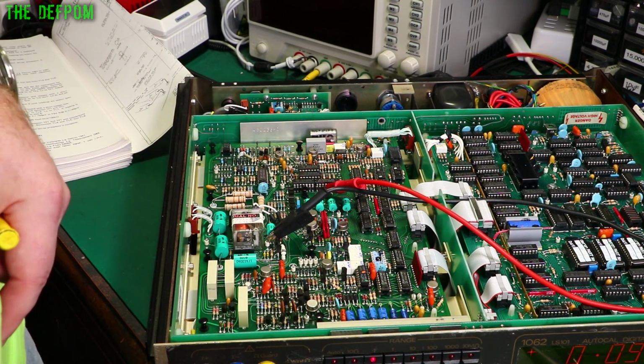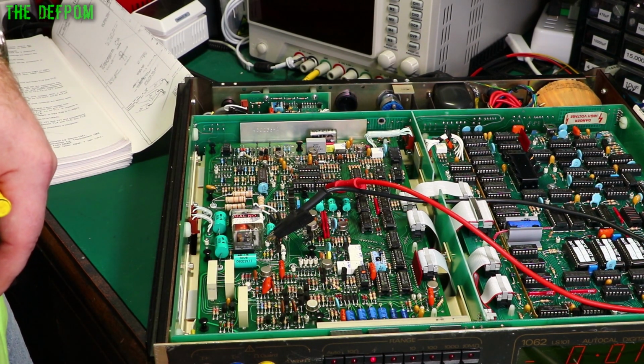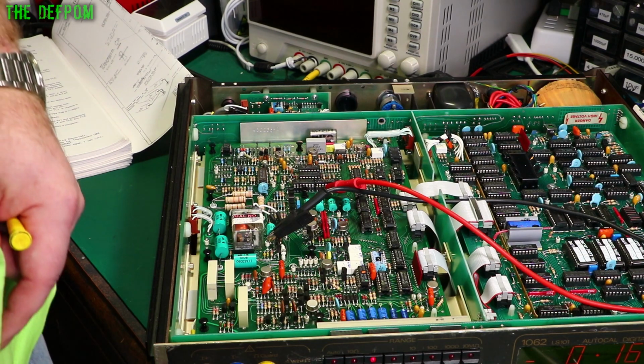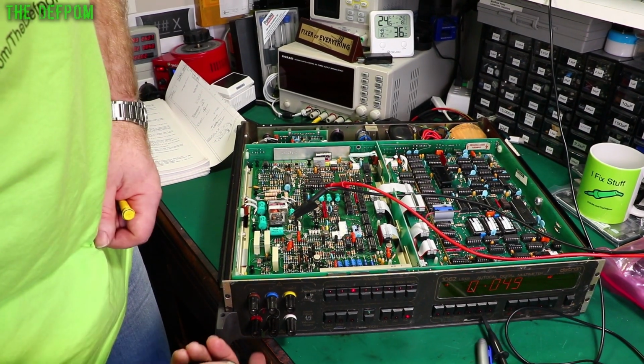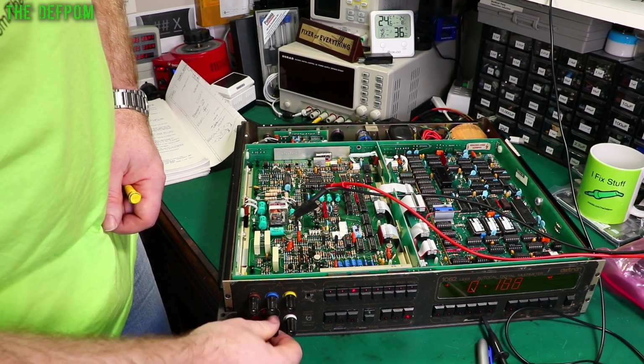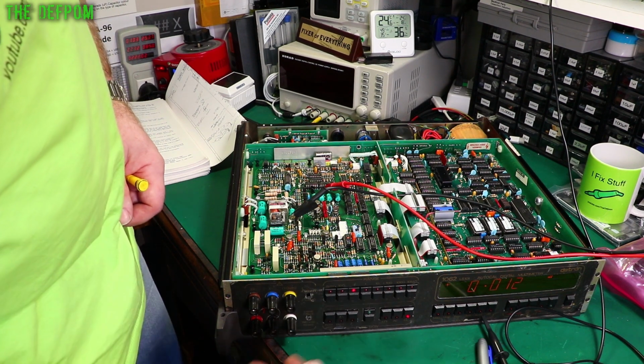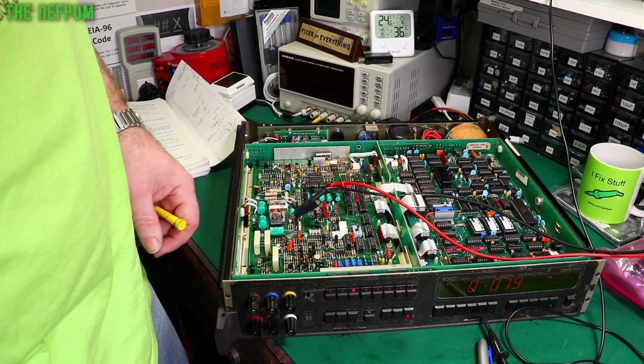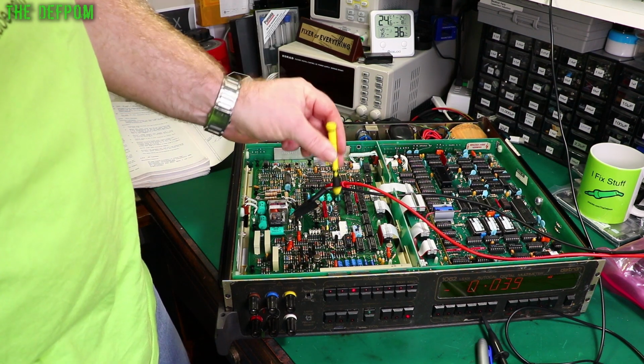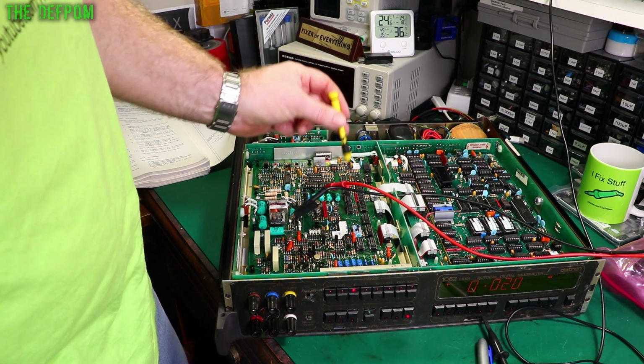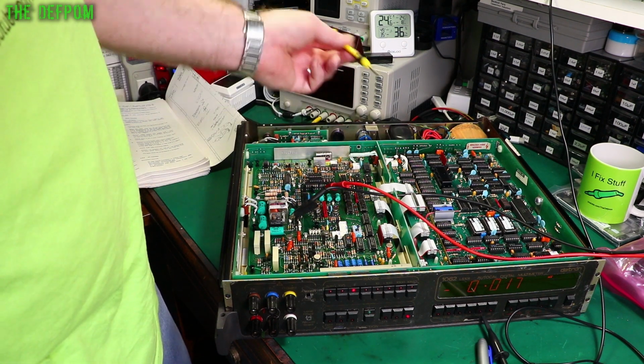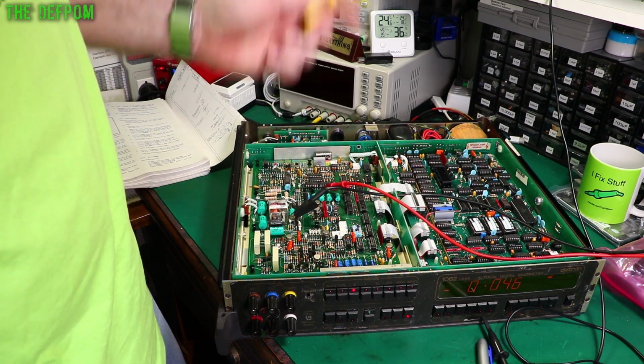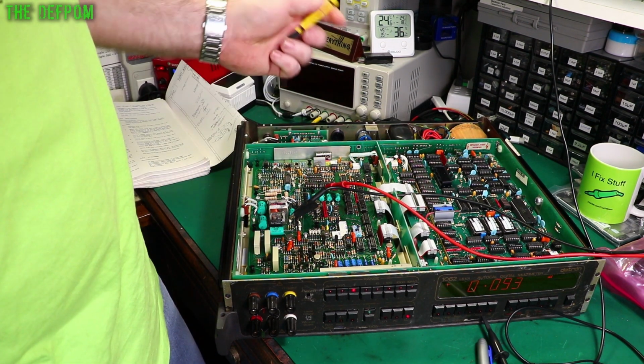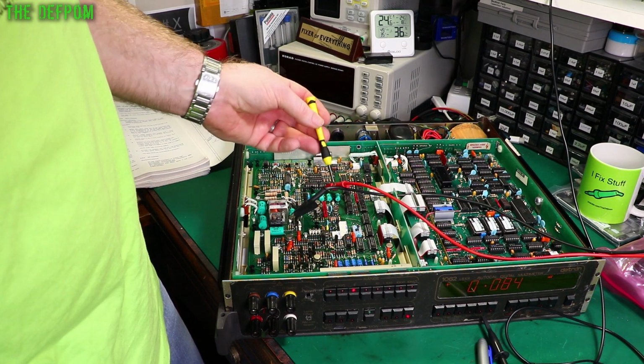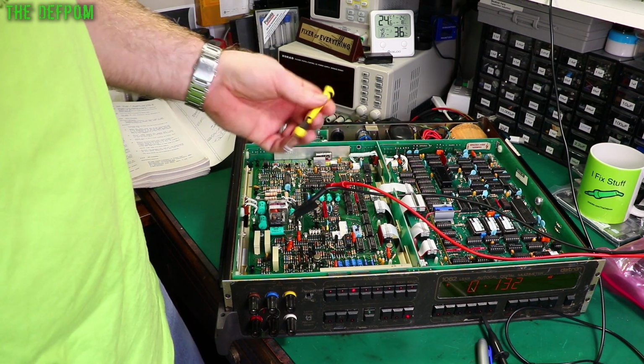And this is with a 10 mega ohm across the inputs with a 10 nanofarad capacitor also across the input, which you can't quite see, it's out of shot. It's down here. So I've got both across the inputs here. That's on DC volts, 0.1 volt resolution. And I'm adjusting, I've already zeroed a couple of these positions, and I've got to adjust R159 for less than 10 millivolts. This is more of a verification because this has got a pre-selected value resistor in here, and that's also been done by the factory.